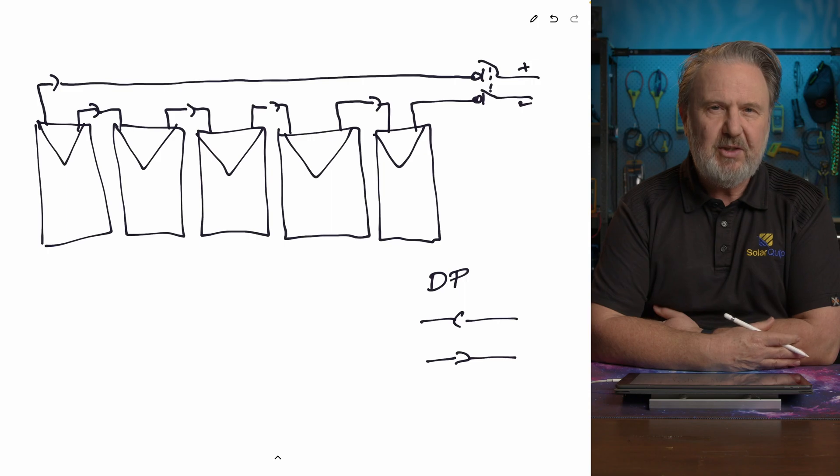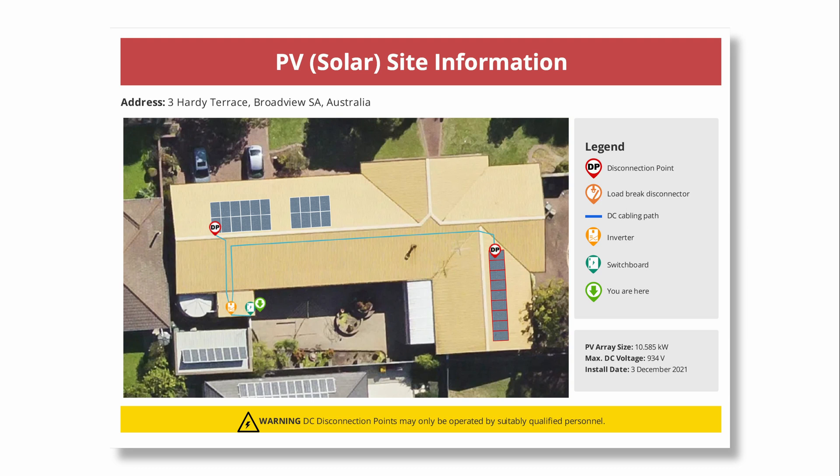The disconnection point is required to be labeled on the site plan — the solar site plan. This is only going to be in newer systems, probably since 2022 or for those adopting the new standard. That disconnection point requires a label at the solar site plan, which should be in a location that can be seen easily — that may well be the main switchboard or near the inverter — and it should identify those points.